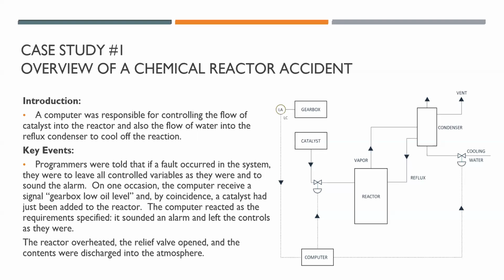So what happened? First of all, this is a system managed by software. You have a programmer designing the software, and they need requirements. They were told that if any fault occurred in the system, they were to leave all control variables as they were.